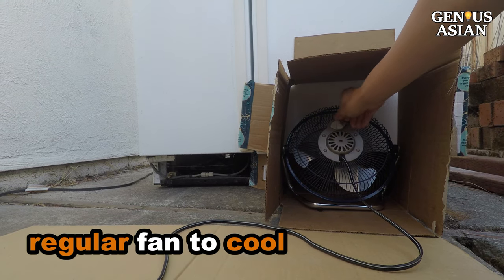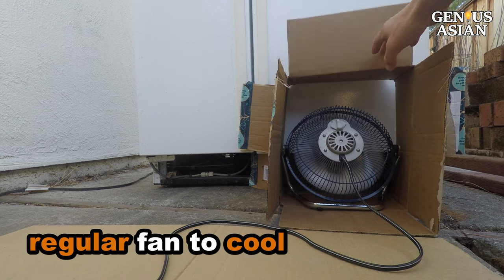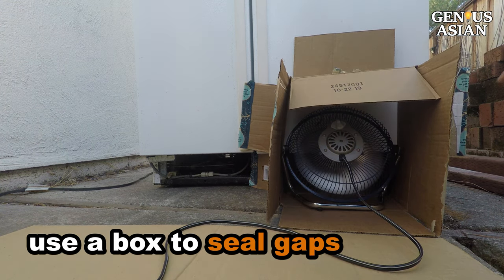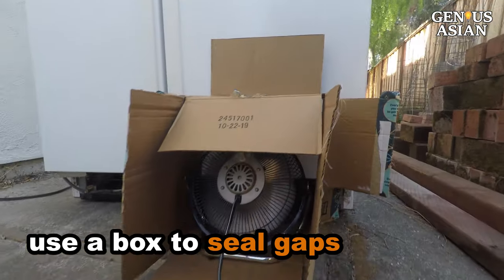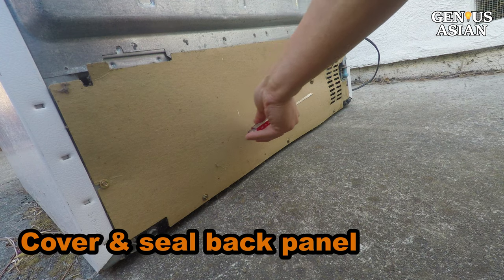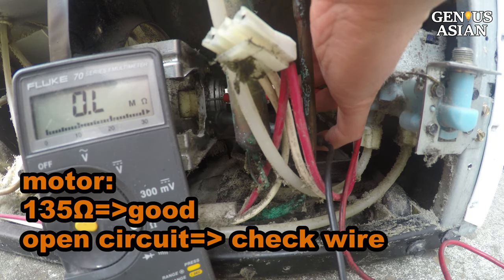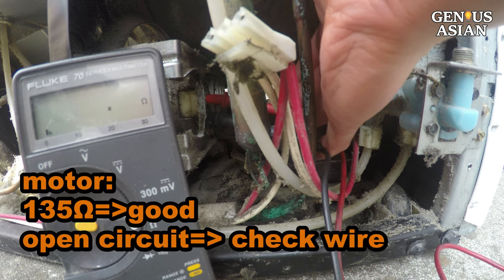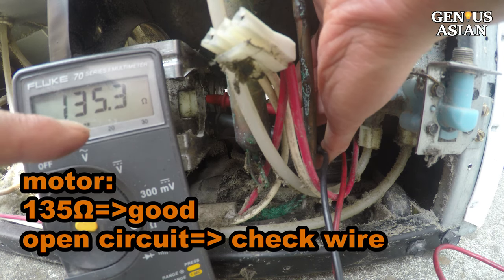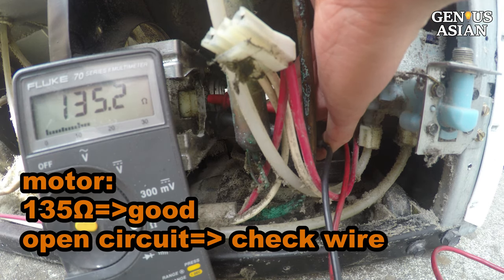While you are waiting for the part, you should use a regular fan to blow air onto the condenser coil. Without this fan, the compressor will be too hot. We can use a box to seal the gaps around the fan and cover the back panel space to have proper convection to cool the condenser coils. When you connect the meter probes to the motor and measure the resistance, if it is an open circuit — not 135 ohms — then you should check the connection or wiring. There is a disconnection somewhere.